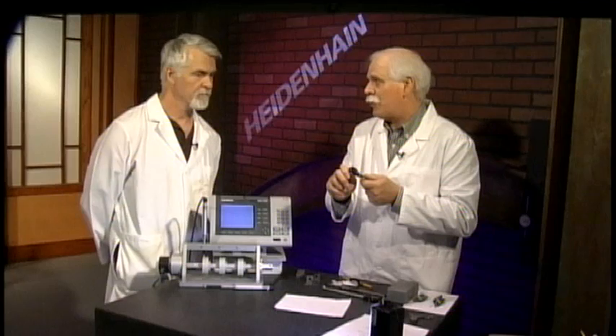So we would leave them unwound, left in their case. That's a good move. The ratchet head itself is usually hardened, so it doesn't have too much trouble. Some brands say to oil regularly, but we don't suggest putting oil in them. If it's in a calibration lab, they're handling that for you. A lot of these ratchet heads, a gear tooth will break now and then, and you'll know it because it'll be slipping on you. Send it in and have the gear head replaced. That's probably beyond most users to adjust themselves, and they'd still need calibration anyway.